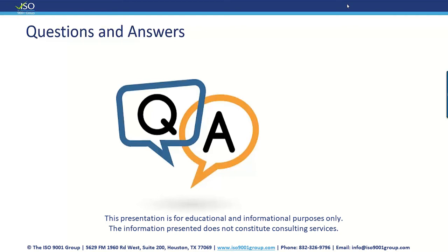But if it's not reading properly, send it out to a calibration lab that's accredited to maybe ISO 17025, and make sure that all of the standards you're using to verify are also calibrated by a calibration lab. But no, I wouldn't recommend you becoming a calibration lab. I would recommend you focus on implementing a verification program to save your company money on calibrations. All right, anything else? Yes.